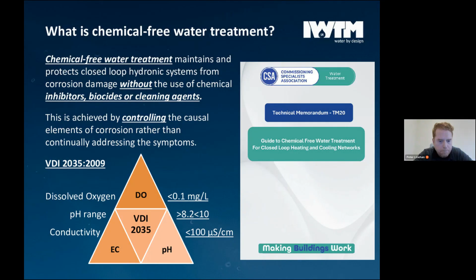I would highly recommend having a look at the CSA's, Commissioning Specialist Association's, Technical Memorandum TM20, which is the first UK guide on chemical-free water treatment for closed-loop heating and cooling systems. So this will give you a good basis on what chemical-free water treatment is, how to pre-commission your system, how to clean up an existing system, and how to maintain a chemical-free water treatment system. So highly recommend downloading that and learning up on it, because it will be the future of water treatment moving forward.